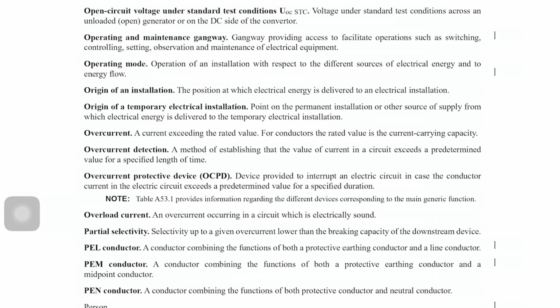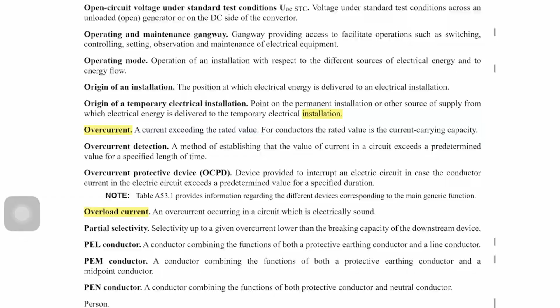I'll touch on obstacle in a minute because I've got a picture to show you. Right, overcurrent. I'll touch on this in part 4 as well. This is a current that exceeds the rated value. For conductors, the rated value is the current carrying capacity, right? Overcurrent is different to overload current. Overcurrent is the umbrella term for overload and fault currents, and there's two types of fault currents. There's earth fault and short circuit, so you need to be familiar with that.